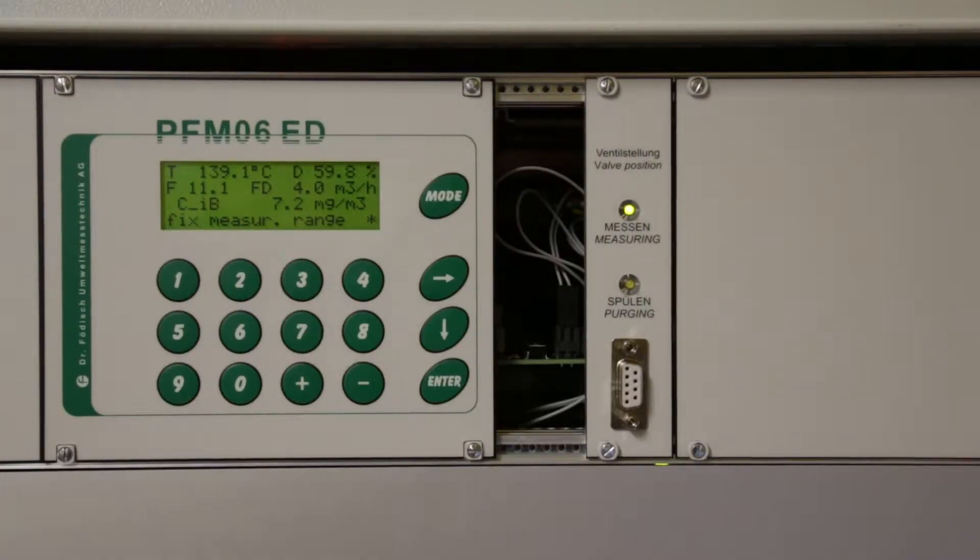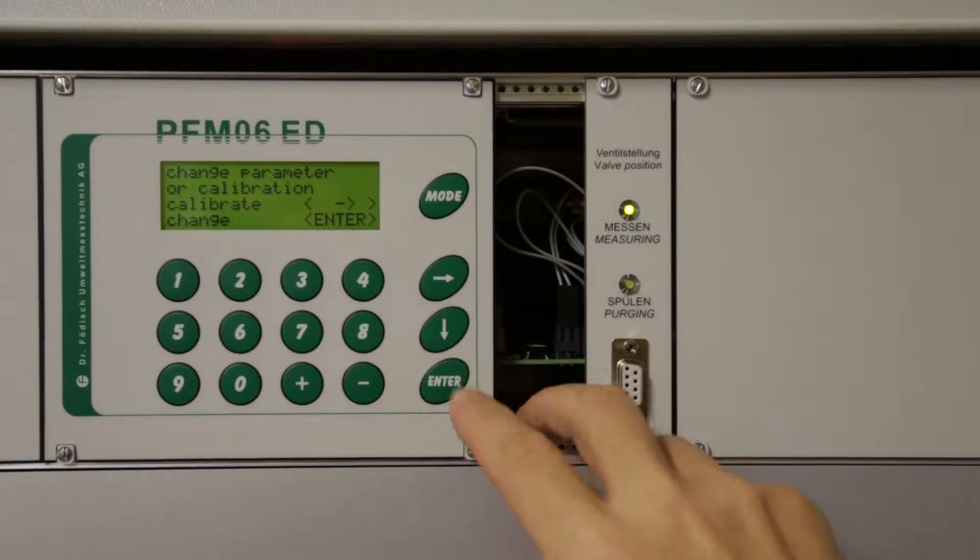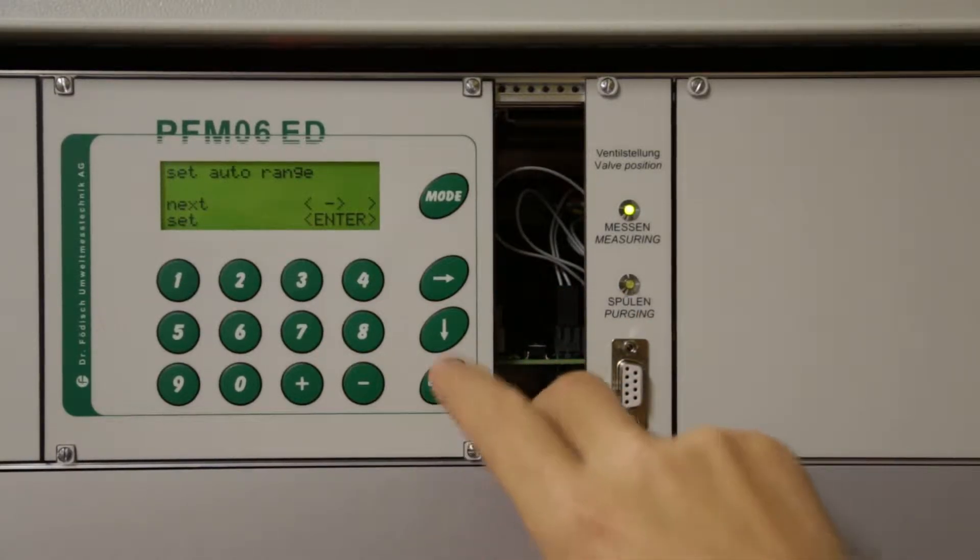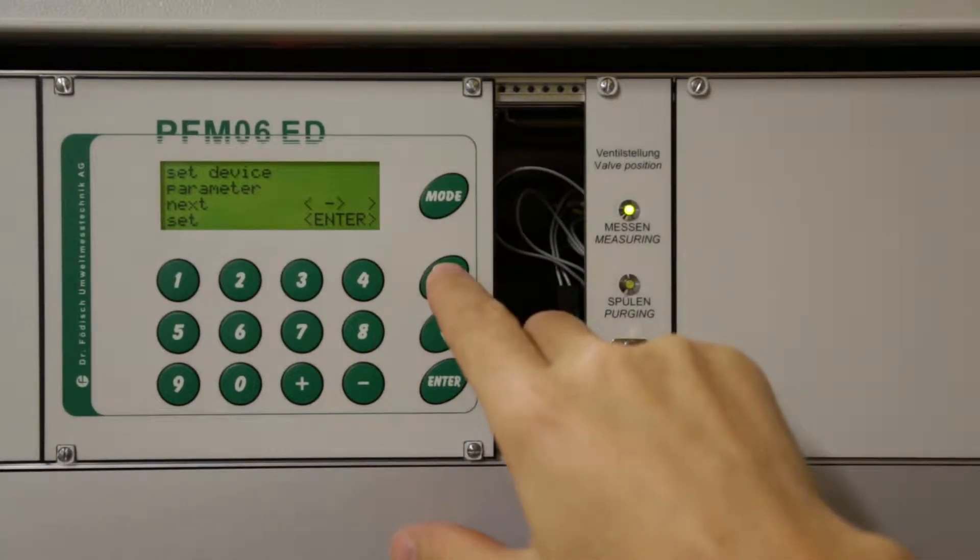In order to check or change the settings of PFM-06ED, remove the cover next to the display and press the button inside. You can change the settings with the control keys. Here you can also enter the calibration factors after a gravimetric reference measurement.